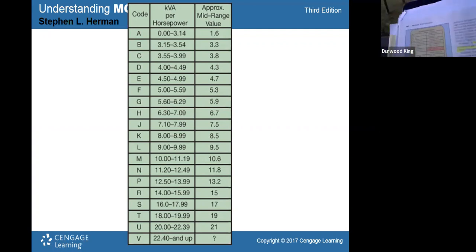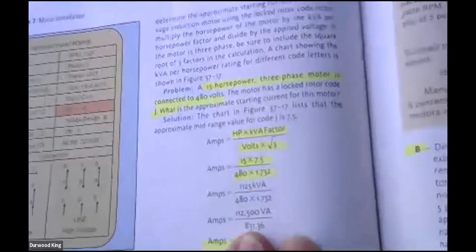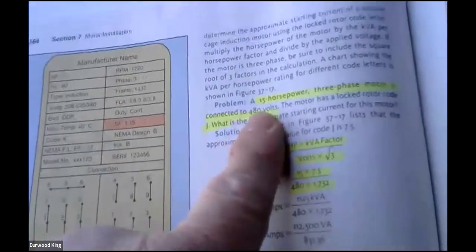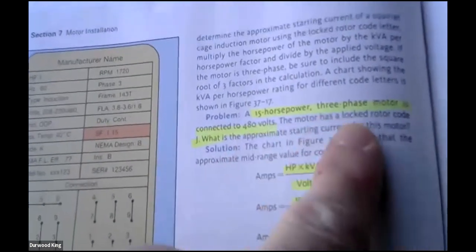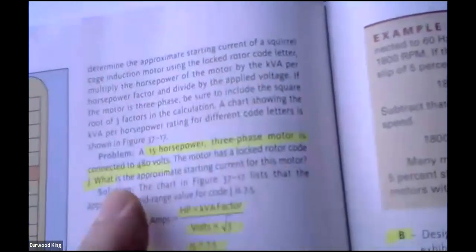If you look on page 364, it's showing you right there. Let me cut screen share off right quick so I can tell if I'm focused right or not. Okay, so now you can see their example is a 15 horse, 3-phase motor at 480 volt, and it has a locked rotor code of J, and the J comes from down here. So the J has a mid-range value of 7.5 per kVA. So for each kVA of the motor rating, it's going to be 7.5 times that.